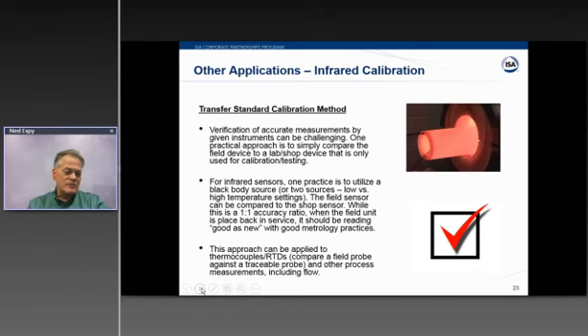Same thing for an RTD, you could use a PRT to make that comparison. And people are doing this with flow meters. You could have sort of a standard flow meter and compare that to your process flow meters. So just wanted to touch on infrared a little bit and how you maintain an infrared sensor and calibration. And this transfer method is another good practice you can employ.